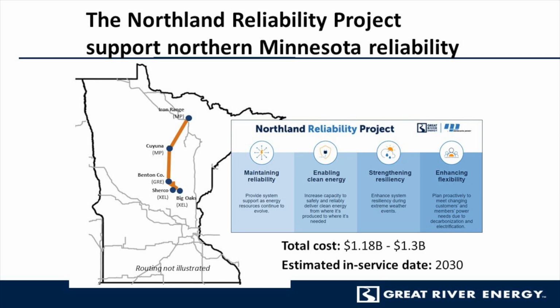What's happened in northern Minnesota over the years is as coal has retired, and you've also got the Boswell units retiring in 2029 and 2035, those retirements happen during the coldest, most dire times of the year in winter when load is increasing. The only way power can go from southern to northern Minnesota is through 115 kV and 230 kV lines, and it's not enough. This 345 kV line provides voltage stability and allows power to safely move up during the most cold and dire high load times of the year. That's why this project is really important to northern Minnesota.